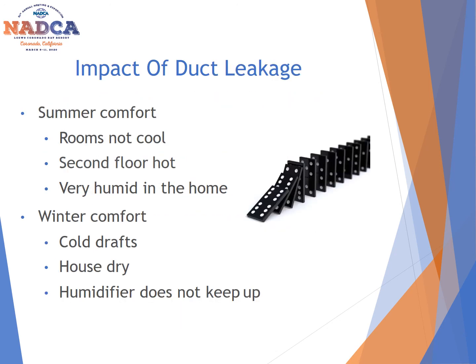We need to understand what the impact of duct leakage is. So when we're talking about the summer months, we're talking about comfort inside of a home or inside of a commercial building. What areas are not getting cooled appropriately? If you're talking about a home on the second floor, why are the rooms up there not being cooled properly? Are you losing some of your cool air into the attic because the ducts are leaking?